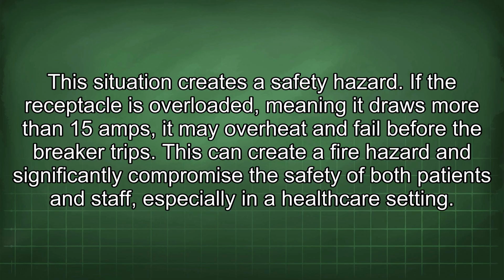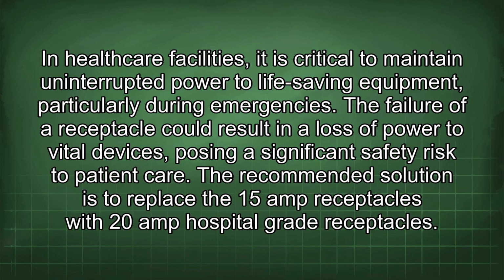If the receptacle is overloaded, meaning it draws more than 15 amps, it may overheat and fail before the breaker trips. This can create a fire hazard and significantly compromise the safety of both patients and staff, especially in a healthcare setting. In healthcare facilities, it is critical to maintain uninterrupted power to life-saving equipment, particularly during emergencies.